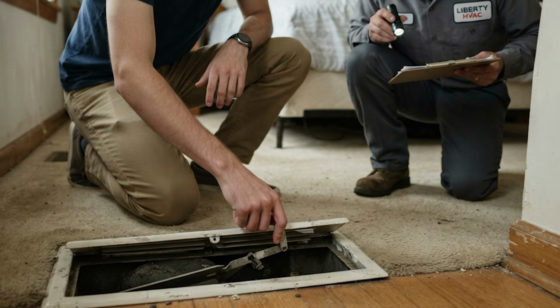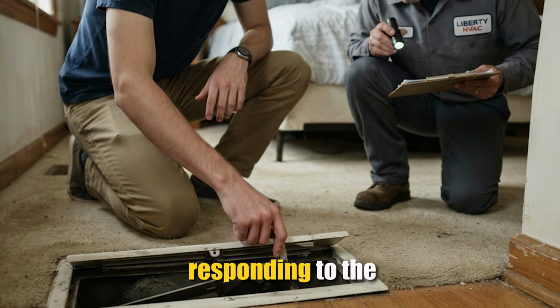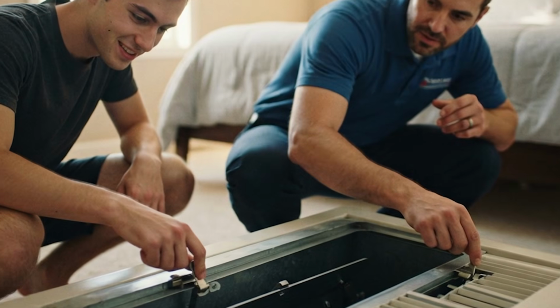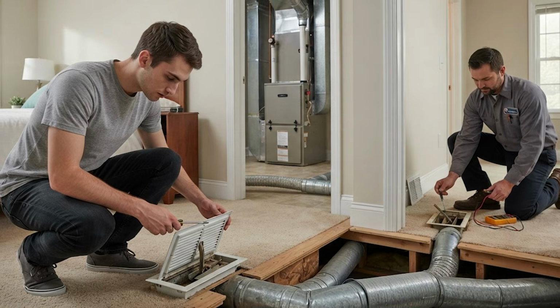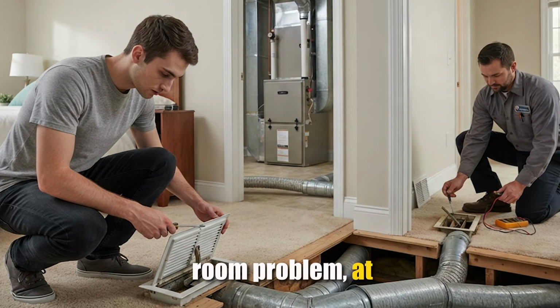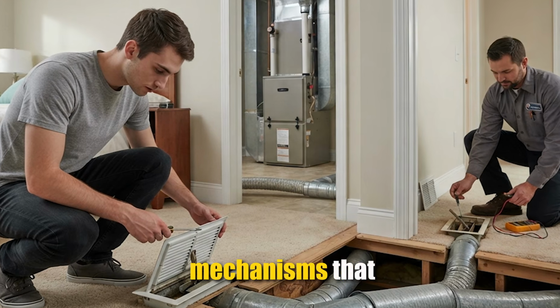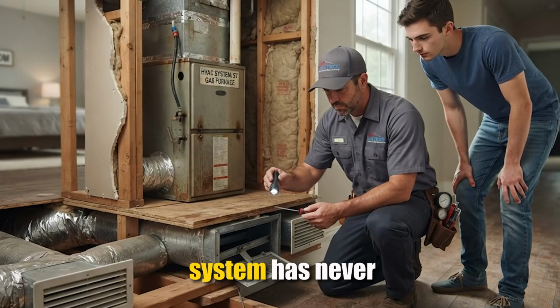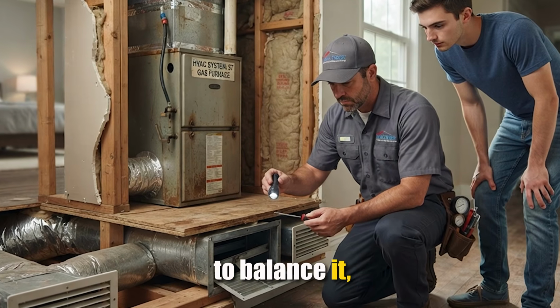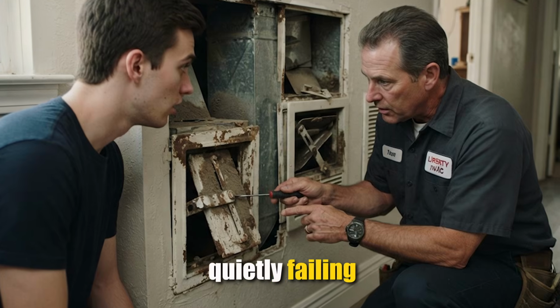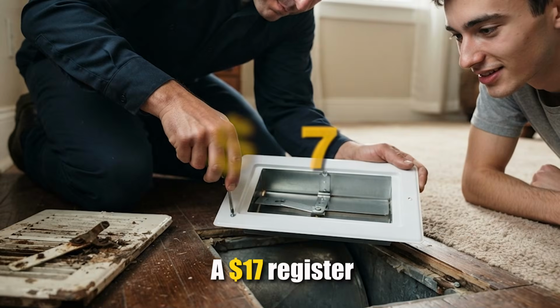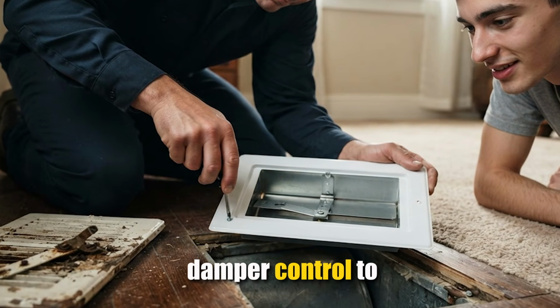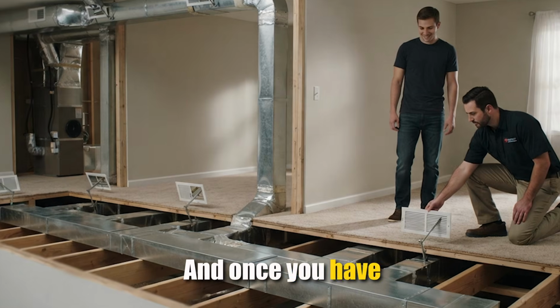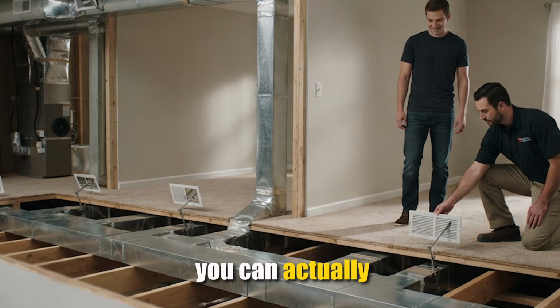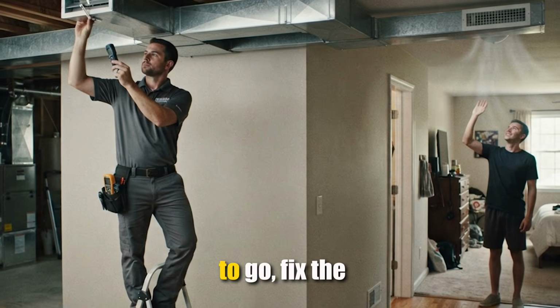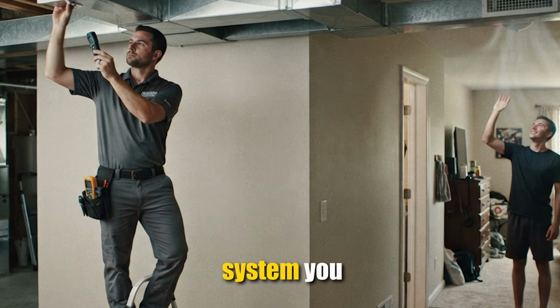And nobody ever checks them. Nobody looks at whether the internal blade is actually responding to the external lever. The lever moves, and homeowners assume the damper is working. In most homes that have a persistent hot room problem, at least one and often several registers have damper mechanisms that are not functioning. The system has never been properly balanced because the tools to balance it, the register dampers, were quietly failing for years without anyone noticing. A $17 register replacement restores full damper control to any vent it replaces. And once you have working dampers on every register in your system, you can actually balance your airflow, direct it where it needs to go, fix the hot room by adjusting the system you already have.